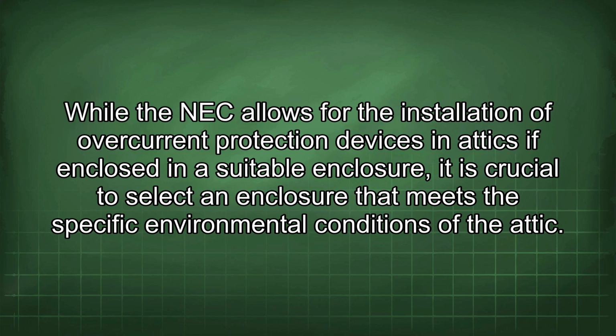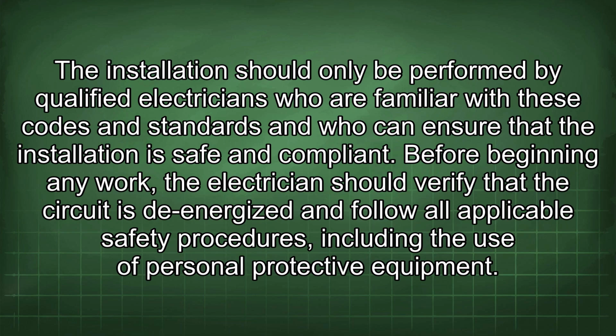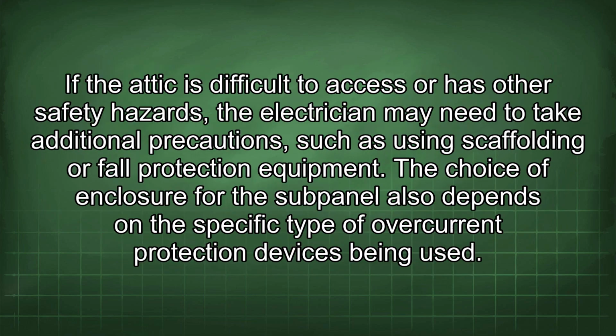While the NEC allows for the installation of overcurrent protection devices in attics if enclosed in a suitable enclosure, it is crucial to select an enclosure that meets the specific environmental conditions of the attic. The installation should only be performed by qualified electricians who are familiar with these codes and standards and who can ensure that the installation is safe and compliant. Before beginning any work, the electrician should verify that the circuit is de-energized and follow all applicable safety procedures, including the use of personal protective equipment. If the attic is difficult to access or has other safety hazards, the electrician may need to take additional precautions such as using scaffolding or fall protection equipment.